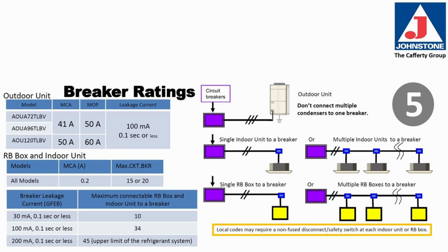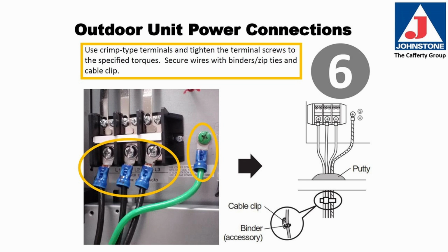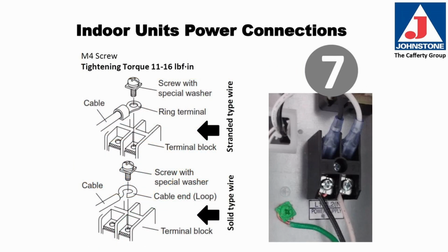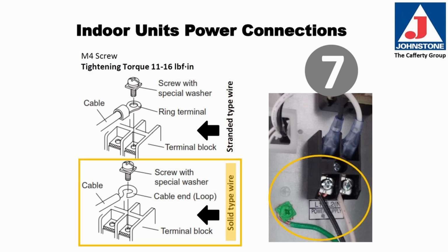Local codes may require a non-fused disconnect or safety switch at each indoor unit or RB box. Again, use crimp-type terminals and tighten the terminal screws to the torque specs that you can find in the installation manual. Secure the wires with binders or zip ties and cable clips. For indoor unit power connections, the M4 screws tightening specifications are 11 to 16 inch-pounds of torque. When you're using stranded type wire, use a crimp type connector to connect the wire to the terminal block. If you're using a solid core wire, make a cable loop on the end of the wire and connect that to the terminal block. Torque specifications are the same.